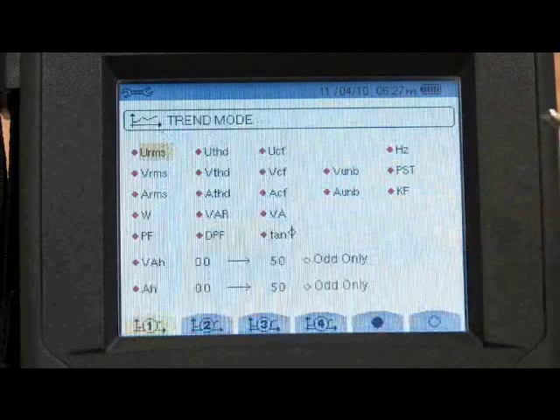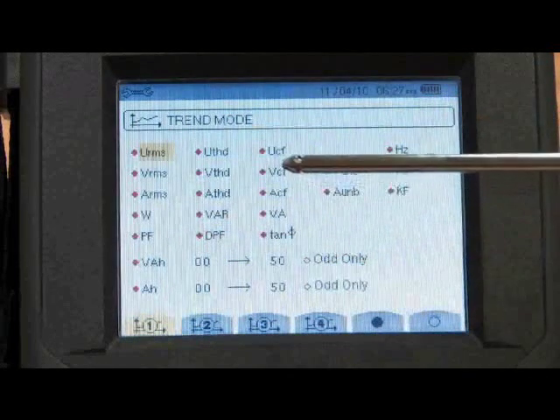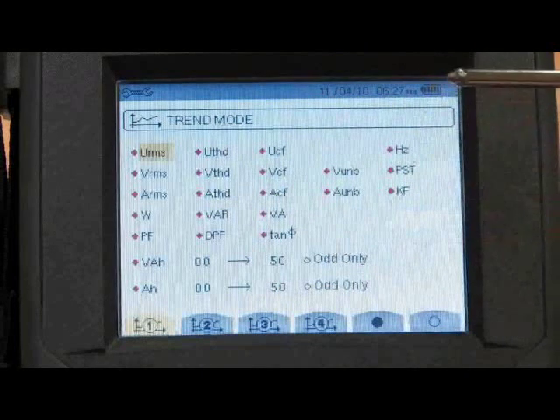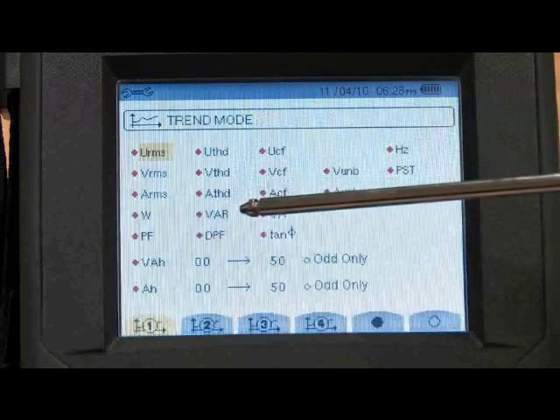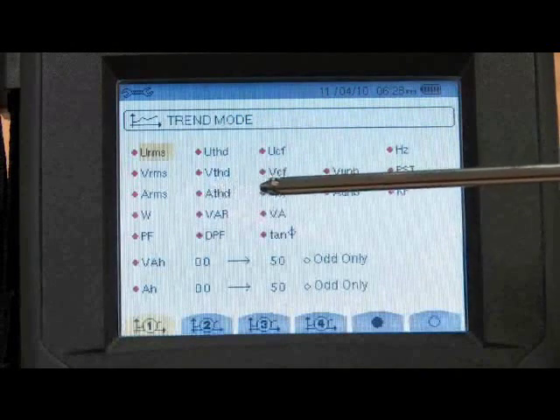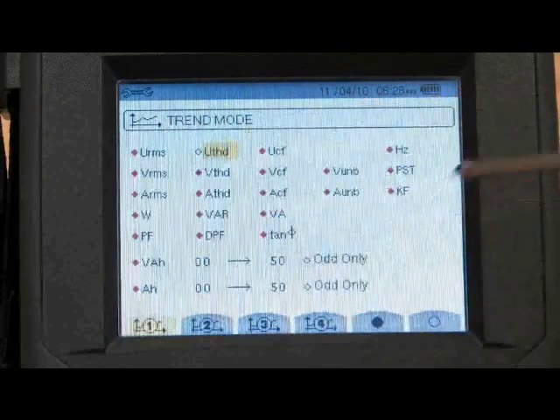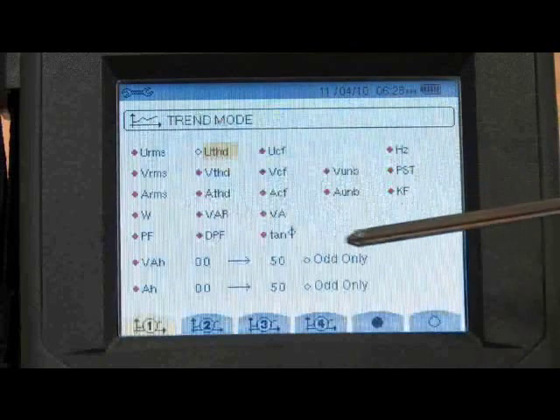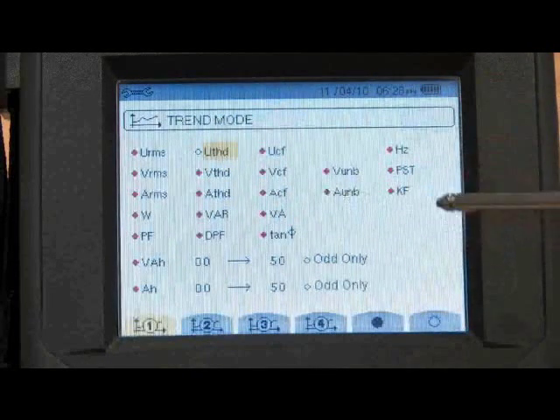In the trend mode that we talked about, this is where I can pick those parameters that we want to record. As you can see from this screen here, there are a multitude of parameters that we can record. The ones that show up as a red diamond have been selected for recording. To unselect the channel, I simply go to it, press the enter key, now that red diamond turned into a white diamond. So I can pick up to any one of 22 parameters or all 22 parameters to record in the trend mode.